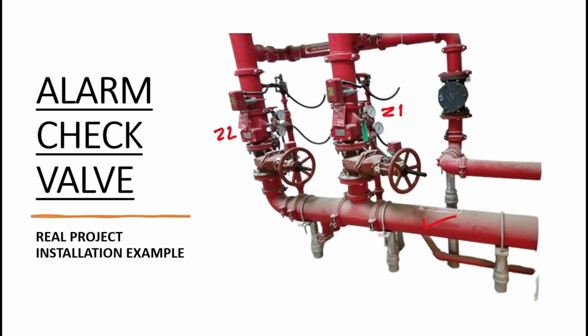So first thing here we have this gate valve. The gate valve with a position device. You can use a butterfly valve also. And then we have this component. So this component is basically an alarm check valve. See the alarm check valve. Okay, and then this is the flow switch. This one is the flow switch, and this is the drain. See the pipe. This pipe is the drain. Okay, these are supports, pipe supports on the floor, and this is actually a check valve for the breeching inlet.